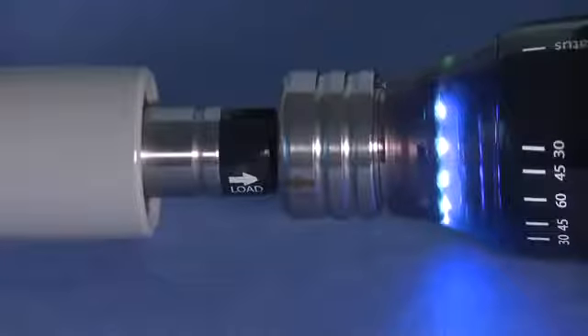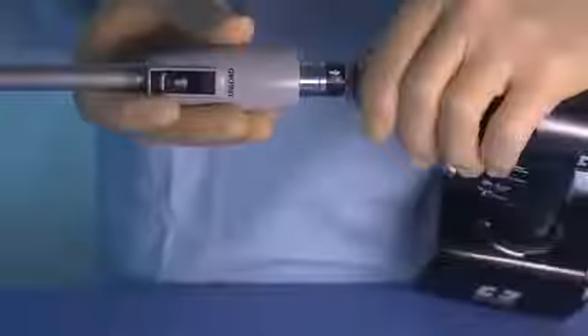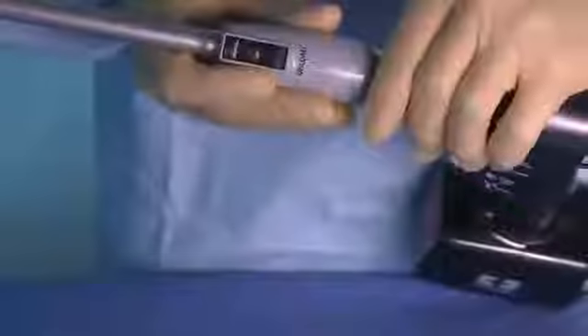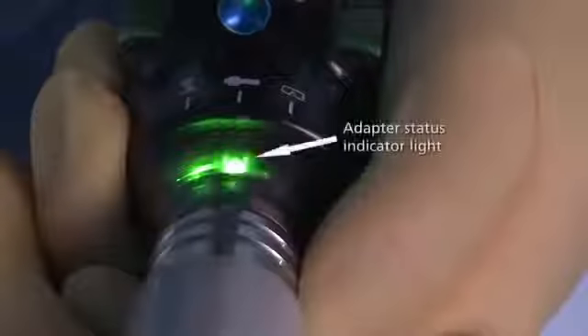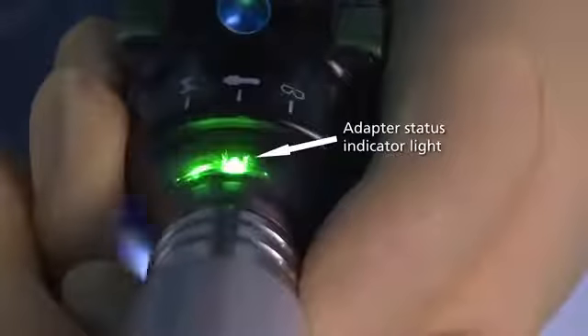Align the loading alignment arrow on the proximal end of the Endo-GIA adapter with the loading alignment arrow on the handle quick connect mechanism. Pull the quick connect mechanism towards the handle while simultaneously pressing the 2 components together until the adapter is fully inserted into the handle. Release the quick connect mechanism. The handle will automatically calibrate the adapter. The adapter status indicator light will steadily flash with a green color while calibration is in progress. The indicator will show solid green when calibration is complete and the handle is ready for Endo-GIA reload attachment.